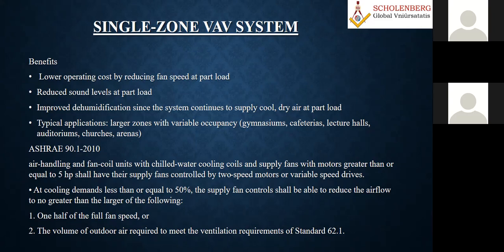And when we go for a single zone VAV system, there are some advantages. ASHRAE 90.1 very strongly recommends this, particularly for fan coils with chilled water coils and supply fans with motors greater than or equal to 5 horsepower. The supply fans shall be controlled by 2-speed motors or variable speed motors. This is what ASHRAE recommends.